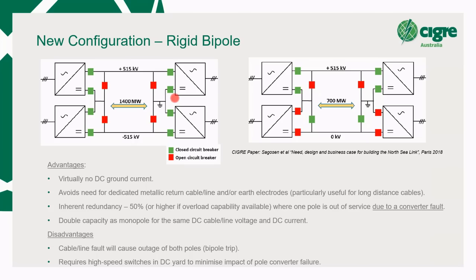If we look at the diagrams, I've put the diagrams up again, and red is an open circuit breaker. So in this case, the converter has failed here. Then we go over to here, the two circuit breakers here have opened and this one is closed. So it's now bypassed that converter, and it is using this line here, which was previously the high voltage conductor, at 0 kV. So the negative conductor or cable is now being used as a metallic return. Awesome, thanks for that. Yeah, I think that clarifies it.